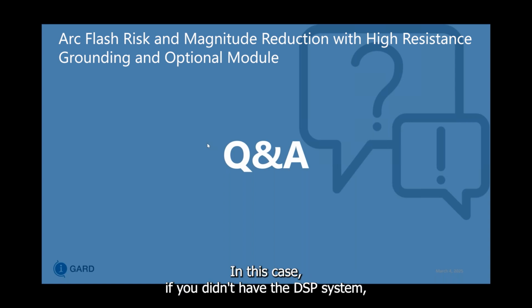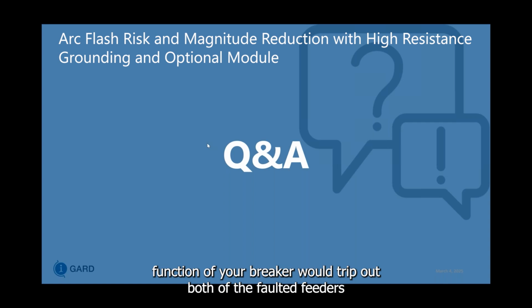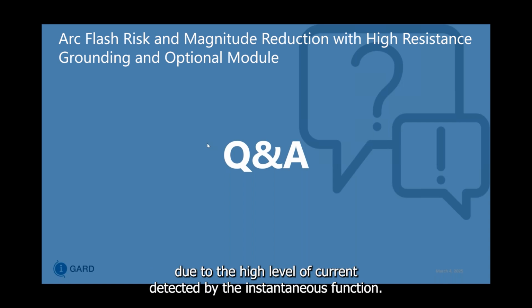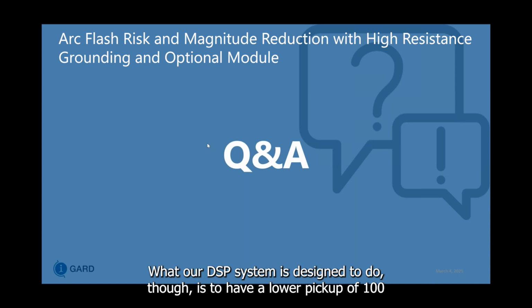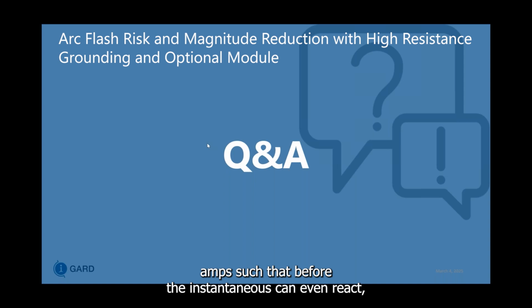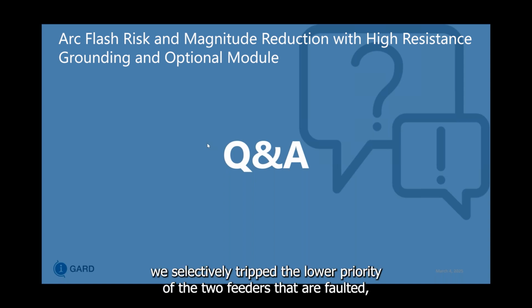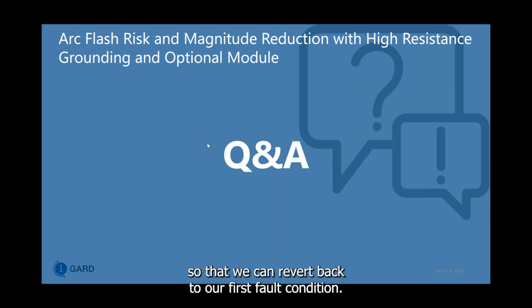In this case, if you didn't have the DSP system, the instantaneous function of your breaker would trip out both of the faulted feeders due to the high level of current detected by the instantaneous function. What our DSP system is designed to do, though, is to have a lower pickup of 100 amps such that before the instantaneous can even react, we selectively trip the lower priority of the 2 feeders that are faulted so that we can revert back to our first fault condition.